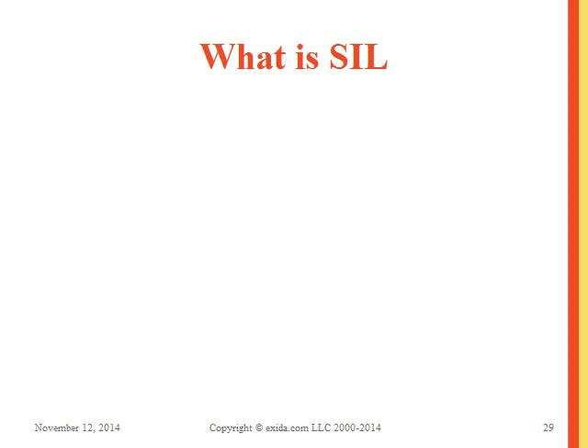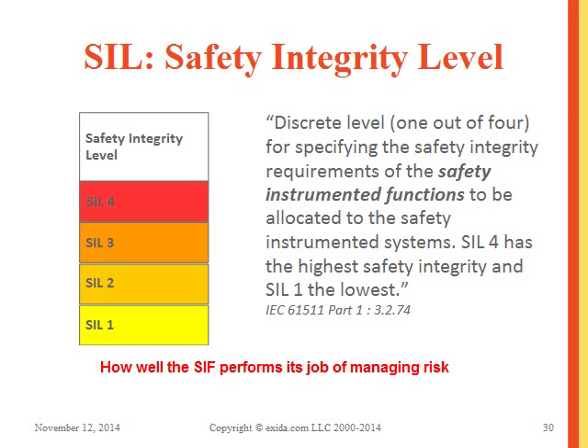A SIL is a safety integrity level. IEC 61511 only defines SIL 1 through 3, with SIL 3 expected to be the maximum level in the process sector, excepting nuclear. For SIL 4 requirements, IEC 61511 refers back to IEC 61508. The graph from 61508 and 61511 shows SIL 1 through 4, with 1 being the lowest and 4 having the highest safety integrity level.